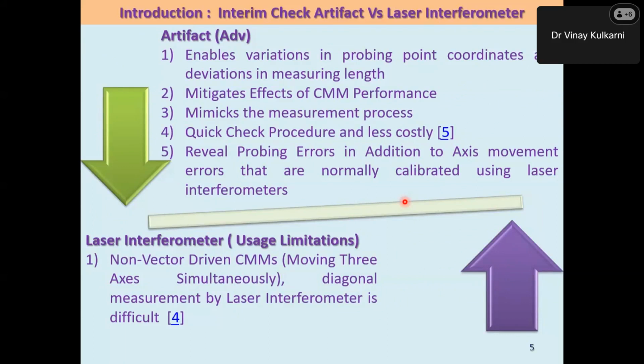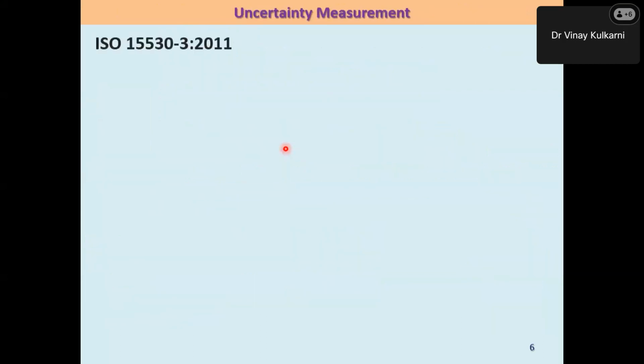Advantage of artifact is it enables the variation in probing point, coordinates, and deviation. It also quickly mimics how we are measuring by using CMM. And because of that, mitigation of the errors in the CMM performance is very easy. At the same time, even if you are using laser interferometer, it's a non-vector driven CMM. That is, diagonal measurement by laser interferometer is really very difficult. That is not possible. At the same time, laser interferometer will not reflect how we calculate the dimensions by using the CMM. So that's a major disadvantage we can say.